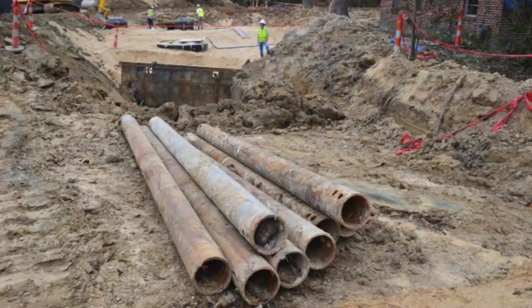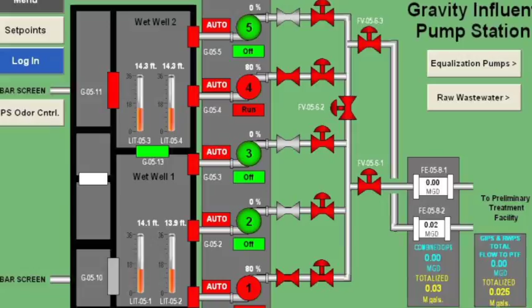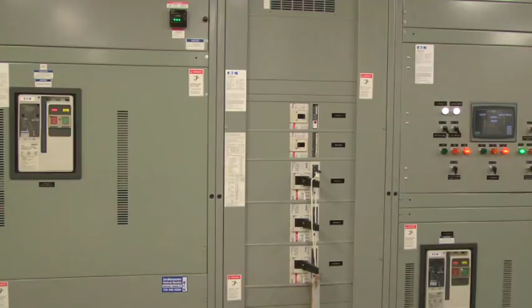A major component of our new wastewater system will be a $30 million SCADA system, which will be installed at all of our almost 500 pump stations. There will be a main central control center as well as an alternate control center located at our emergency operations center. We will be able to control 38 major pump stations, direct flows into storage and back into the systems, as well as monitor all of the pump stations.